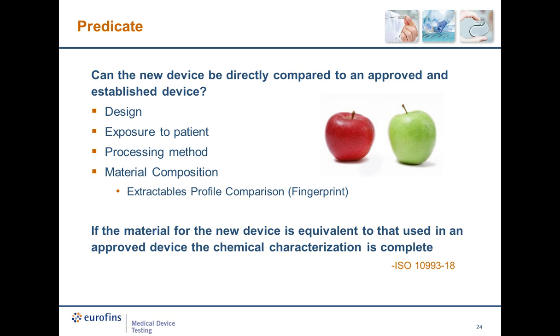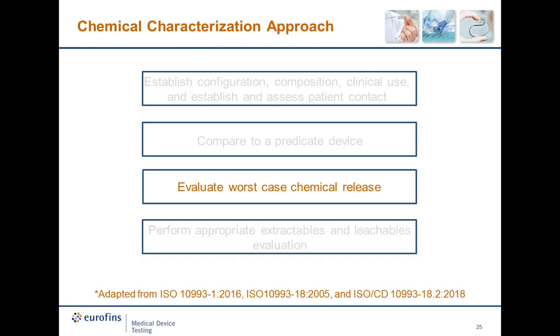Obviously, not all comparisons are as simple as the example I just provided, and one avenue to explore to aid in comparison is the extractables profile. If a sponsor can demonstrate that the extractables profile of the new device is equivalent to the predicate device, this can go a long way in establishing chemical equivalence. I will discuss this extractables profile comparison when I address extractables and leachables later in the presentation.